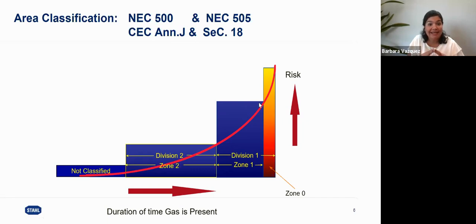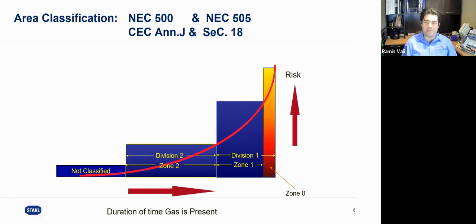I know, Ramin, in Canada you have customers that use divisions and customers that use zones. It's very common to see both of them. What's your experience in that situation? Some of the friends who used to use the class division concept in the past, and are now switching to the zone system, tell me that they have more options to choose the right product with the zone system. A very typical example of it is HMI.